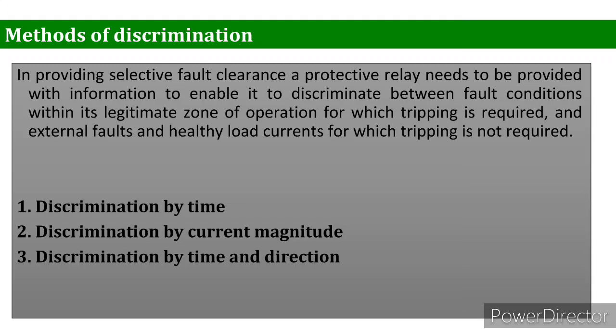In fault clearance, a protective relay needs to be provided with information to enable it to discriminate between fault conditions within its legitimate zone of operation for which tripping is required, and external faults and healthy load currents for which tripping is not required. In the method of discrimination, some information must obviously be derived from the available electrical quantities of current, voltage, and the phase angle between them, measured at the time of fault.